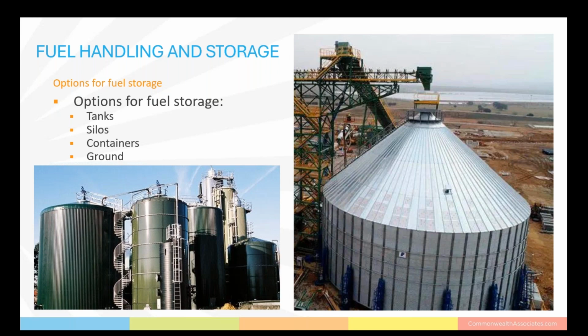If the CHP design utilizes a boiler for heating process, coal or biomass would most likely be the fuel. Most common forms of biomass are wood pulp and crop residue. But biofuel could be anything from ethanol and biodiesel to a pelletized fuel that would typically come from forestry and farming industries. Any of those biofuels will require accommodations for offloading and stockpile locations. They could be stored in tanks, silos, or simply on the ground. These biofuels will also require space for the conveying equipment needed to move the material from the storage to the boiler house.